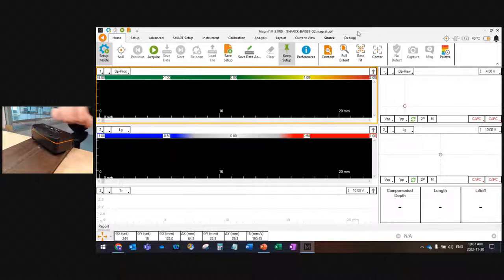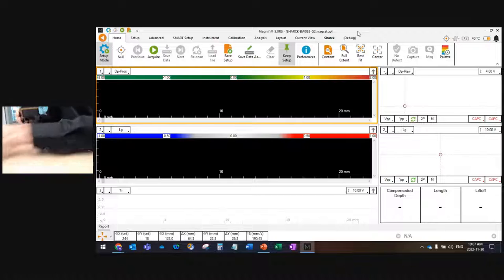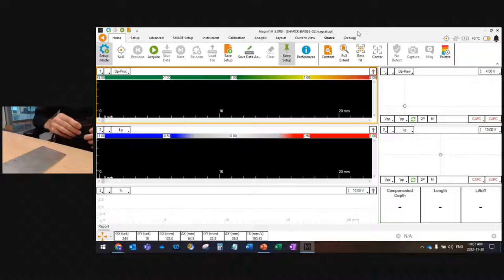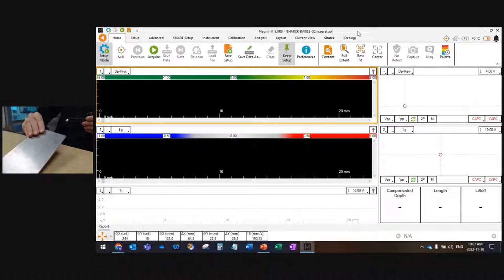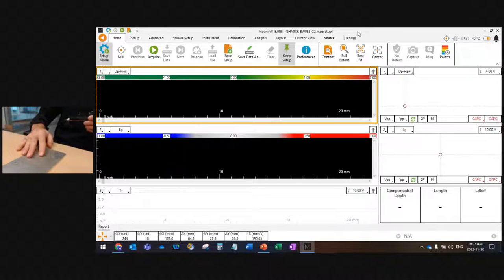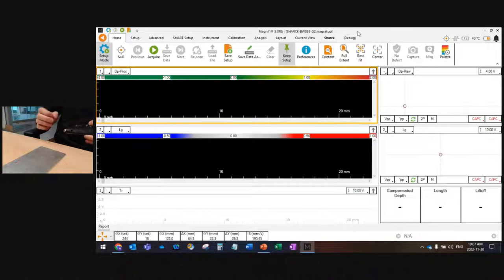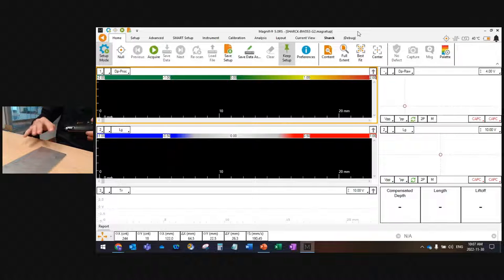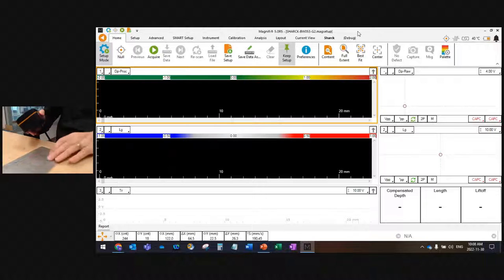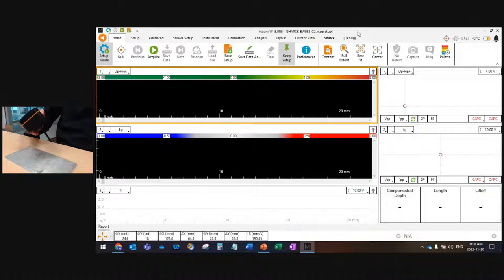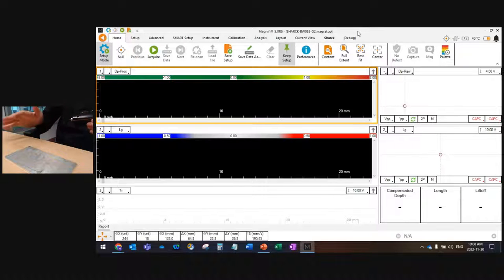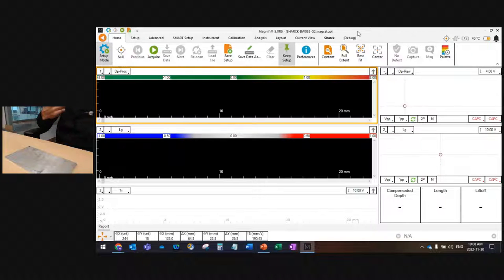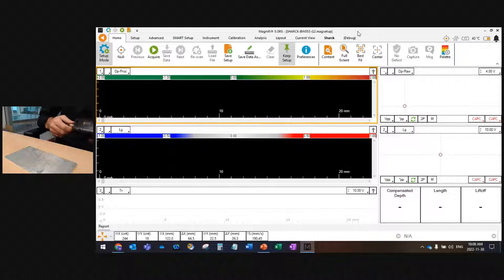First thing I will do, I will calibrate my probe on this small aluminum plate that you have here. This is just a standard aluminum that we use for calibration. The reason why we use aluminum instead of carbon steel is that aluminum is extremely stable in terms of surface conductivity. It doesn't have any magnetic permeability. You cannot reliably calibrate your probe on carbon steel because of all the changes of magnetic properties, all the changes of conductivity. This is why we use aluminum.